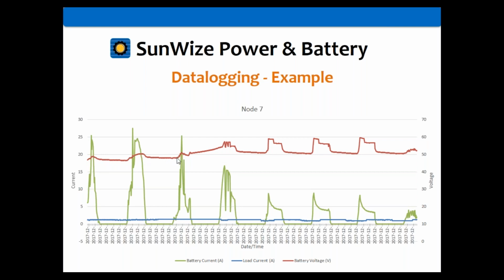If they had continued running like this, the battery plates would have sulfated because the battery wasn't getting fully charged. They never would have known this because the load wasn't going down. So the system was limping along, but they could have had problems. If they had encountered bad weather, the system could have gone down, but worse yet, they probably would have sulfated the battery plates and caused damage to the batteries.